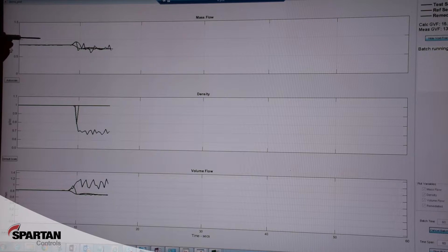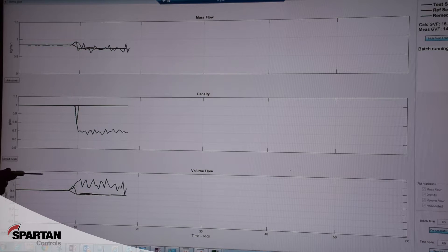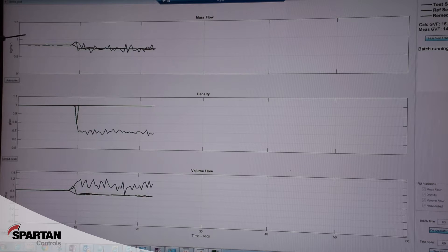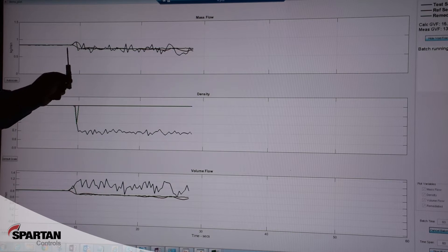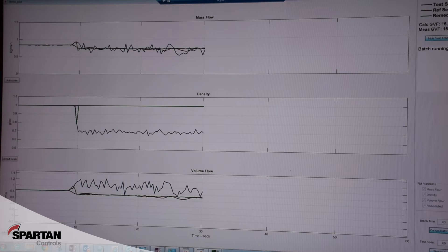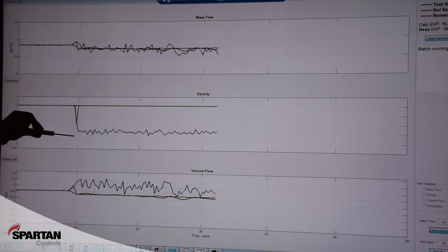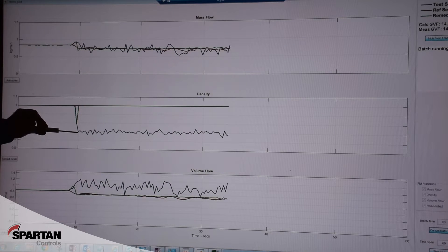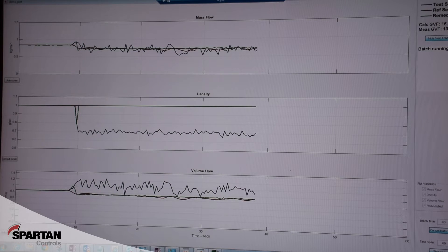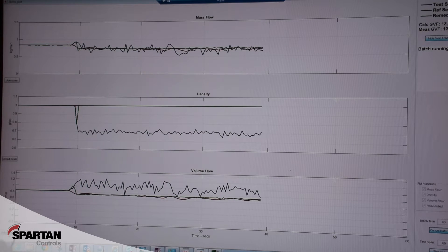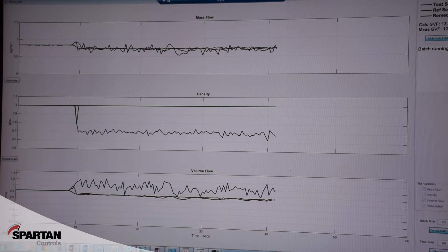Here is the example of my mass flow, my density, and my volumetric flow with both test and reference meters. The mass flow doesn't make much of a change after I injected the air — the air was injected approximately at this point. What really makes a difference is my density of my test sensor drops off considerably, and then of course my volumetric calculation is also just as much in air, but on the high side.